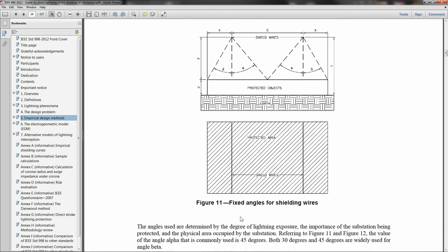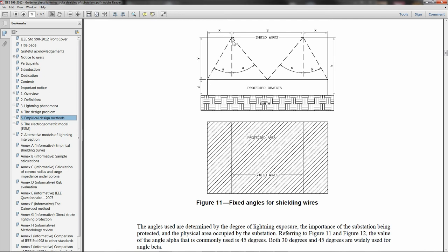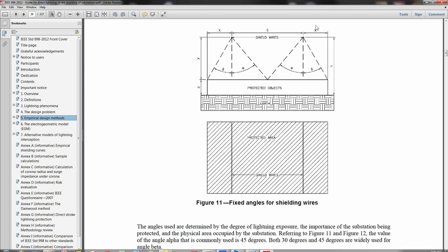Below here are their recommendations for the angles alpha and beta. Angle alpha is generally taken to be 45 degrees where these two shield wires are adjacent to each other, and then the angle beta can be either 30 or 45 degrees. In our case we'll be using 30 which will recognize that the shielding is not as strong where you have no overlapping shield wires. So with that we will go ahead and begin our design.